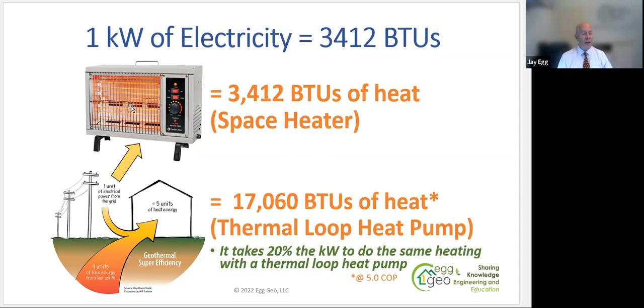So an electric space heater that you can buy and put under your desk or in your bedroom will burn 1 kilowatt of electricity and deliver 3,412 BTUs. A geothermal heat pump will use 1 kilowatt of electricity to run a heat pump, not to burn electricity. It runs a pump. The pump is a compressor that pumps heat from the ground into the space. So for 1 kilowatt of electricity, you will get 5 kilowatts because it's going to pump 4 kilowatts of energy from the ground or from a thermal energy network, delivering a grand total for the same energy, 17,060 BTUs of heat into the space.